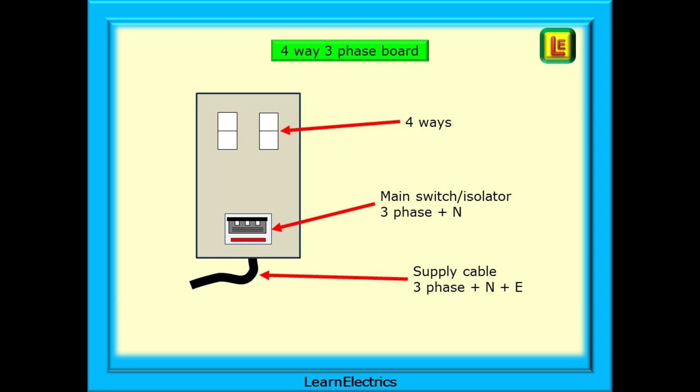There will be a main switch or isolator which will be either three-phase only or three-phase plus neutral. This is different to domestic electrics where the breaker must switch off line and neutral at the same time for the safety of the occupants. With industrial electrics, it's assumed that persons working at the board are suitably skilled persons, so some main switches are just three-phase without a neutral.